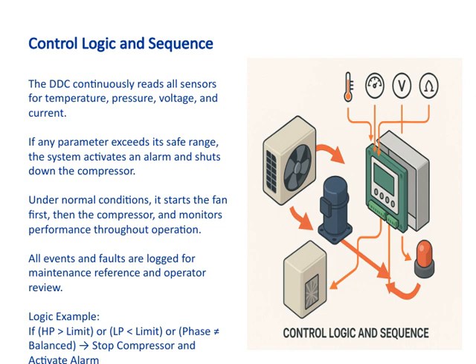Under normal operating conditions, the control logic starts by turning on the fan first, which helps with cooling. Then it starts the compressor. Throughout the operation, it keeps an eye on performance metrics to ensure everything runs smoothly. All events, including normal operations and any faults, are logged. This logging is vital for maintenance and for operators to review what's happening during each cycle.